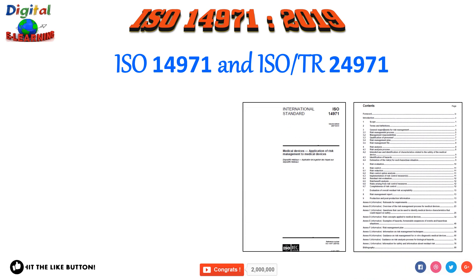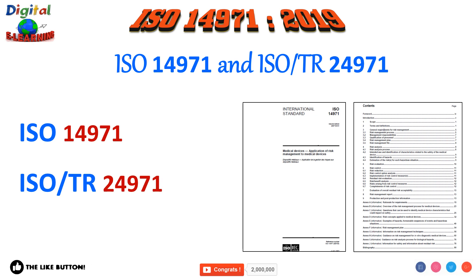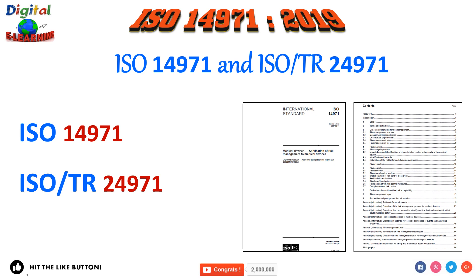ISO/TR 24971 is a guidance document developed in parallel with the revision of ISO 14971. It has the same structure and number of clauses as the main ISO 14971 standard and helps to understand and implement each requirement. The standard is normally reviewed and revised every five years.